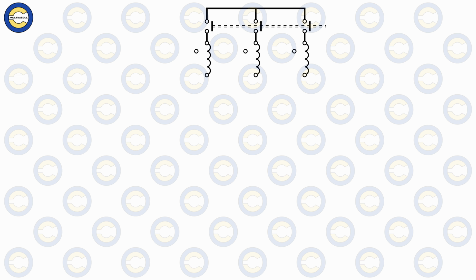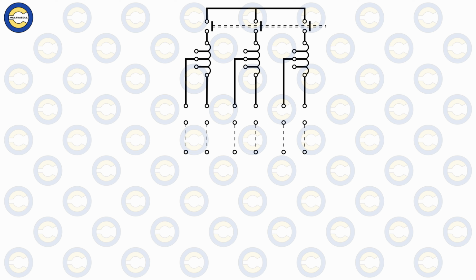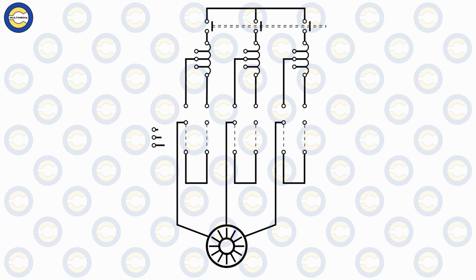The first point of understanding is that when large induction motors are started directly on board ships, they draw a very high starting current. This starting current can be almost 5 to 7 times the full load current. This can cause voltage drops in the system and also mechanical stresses on both the motor and the machinery that it is supposed to drive, for example the pumps, etc. Now, to limit this high inrush current, different types of starters are used on board ships, one of which we are referring to today is the auto transformer type starter.